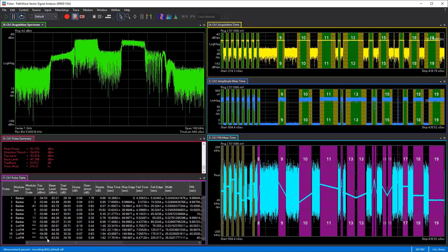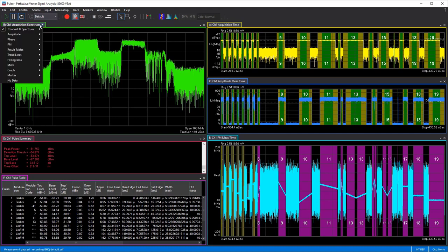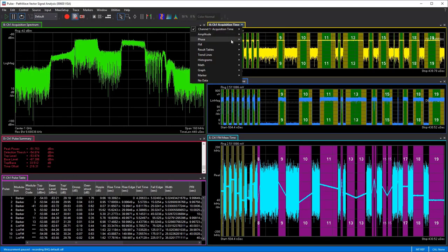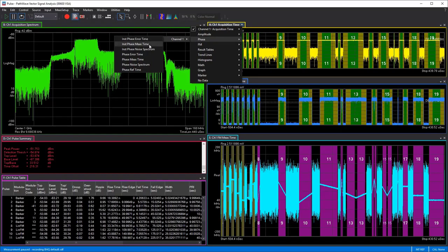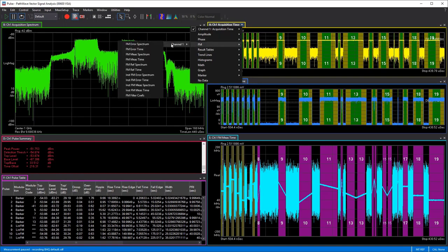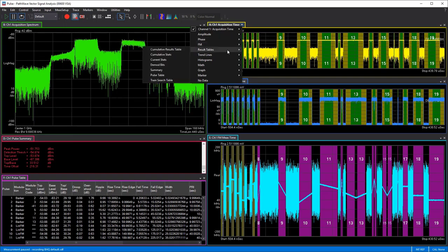So that's a quick overview of the default traces. You can change any trace by clicking on it and selecting the down arrow. This lets you change the trace type — for instance, you can see all the different spectrum traces available. On channel one you can look at amplitude error time, measurement time, reference time, and so on. You can also look at phase traces, and similarly FM traces along the same lines.